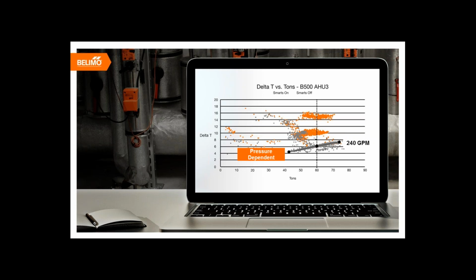You can see there are many plots along this axis, but the average amount of flow needed was 240 GPM. Next, we turned on the feature of the Energy Valve, making it a pressure-independent valve. We used the flow meter along with the analog control signal to keep the flow constant instead of allowing overflow based on set point. When we enacted the pressure-independent feature of the Energy Valve, we were able to maintain the same 60-ton load with a reduced flow of 144 GPM.